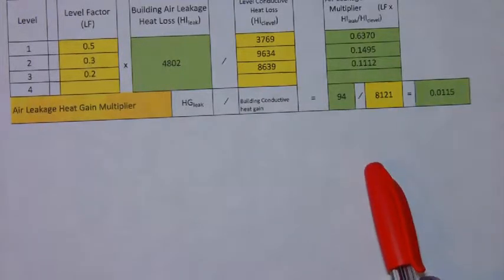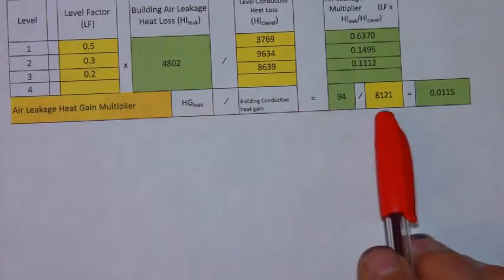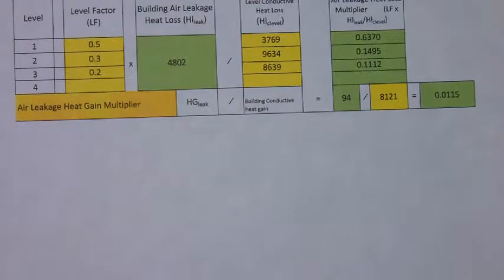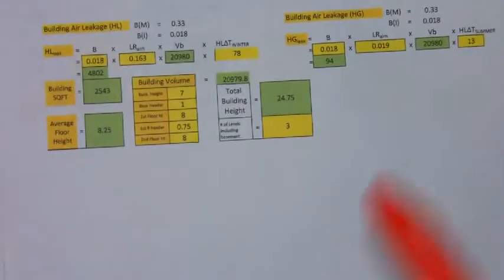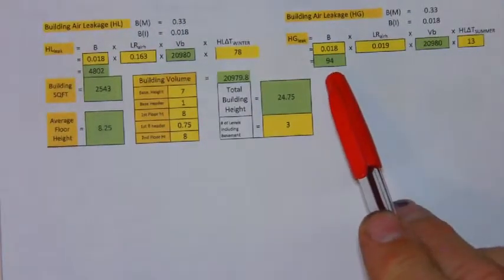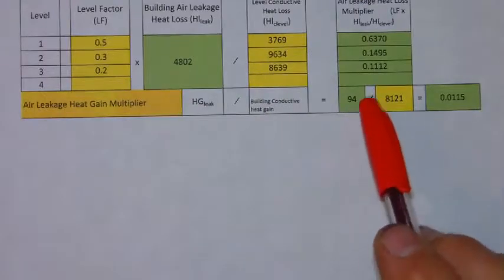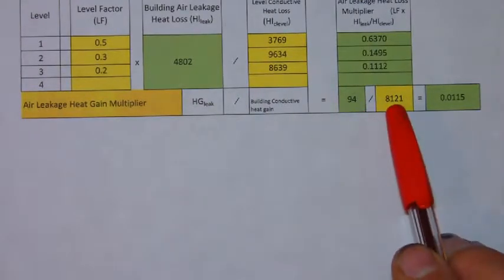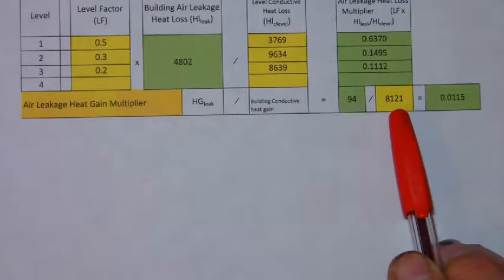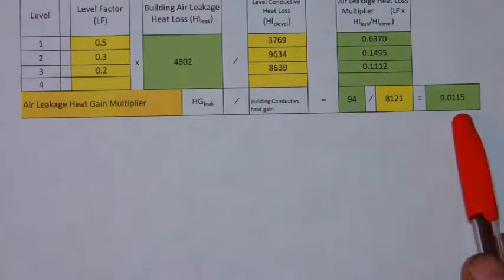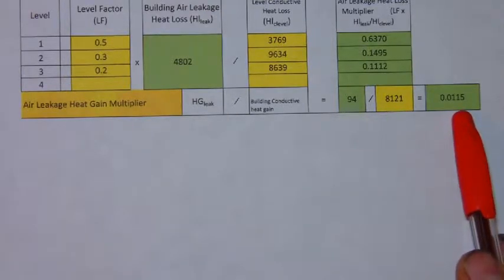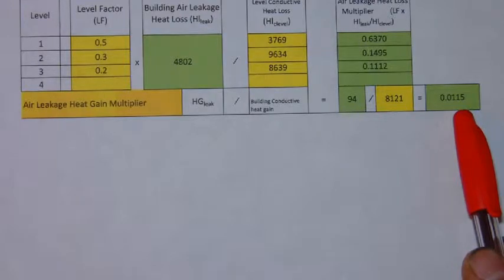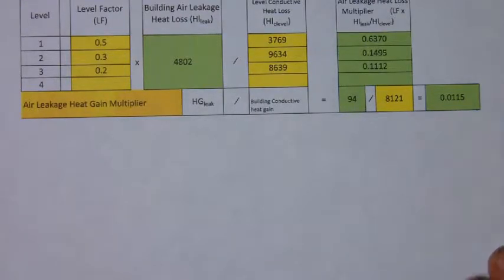And you follow the same process for the cooling. You take the cooling air leakage that you found here, substitute it into the equation, divide by the total heat gain of the building and we get an air leakage multiplier of 0.0115.